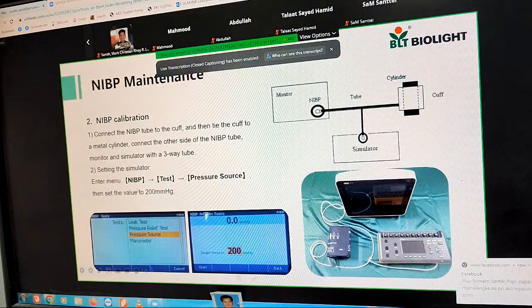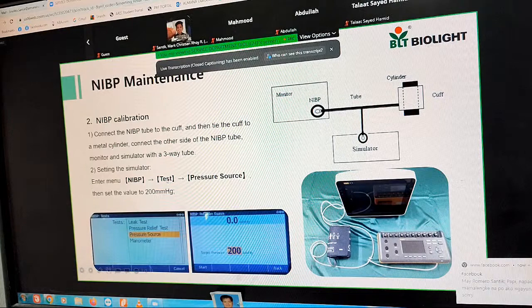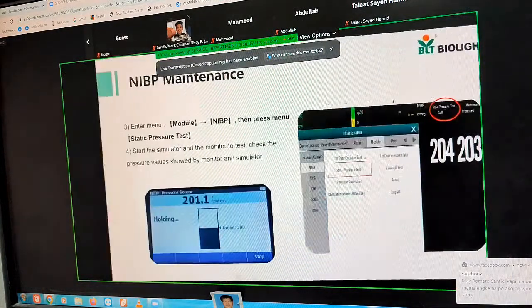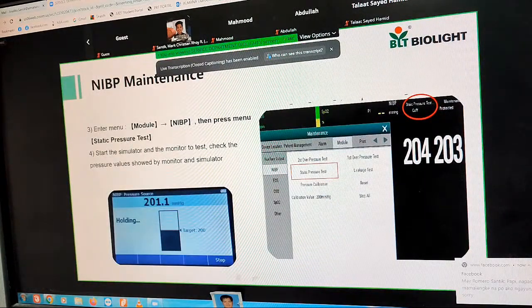And second, we need to set up the simulator. We go to the NIBP menu and choose the test, and we can see the pressure source, and we set the value to 200 millimeters of mercury and go next. And we go to the monitor manually. We choose the module, NIBP, and the pressure manual. We can see the menu has a static pressure test.